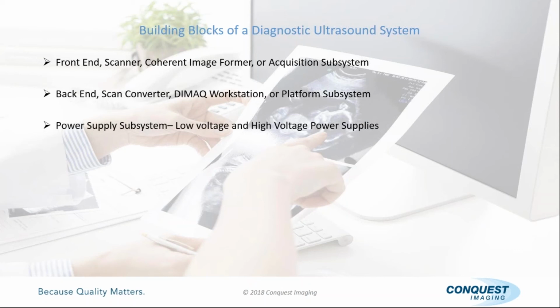These are your three main subsystems on any ultrasound: power, front end, back end. I like to educate people - when you walk up in front of a system trying to figure out what's wrong, one of the best things you can do is try to eliminate two-thirds of your system. If I know it's not a power problem, and I know it's not a front end problem, now I'm only troubleshooting whatever components make up the back end. That's exactly how I approach any problem when troubleshooting an ultrasound - I try to eliminate 2 out of the 3 main subsystems.